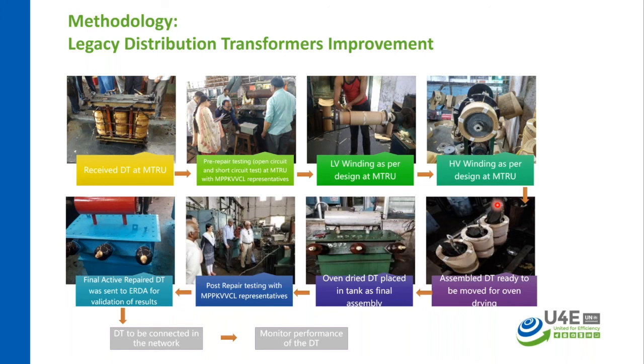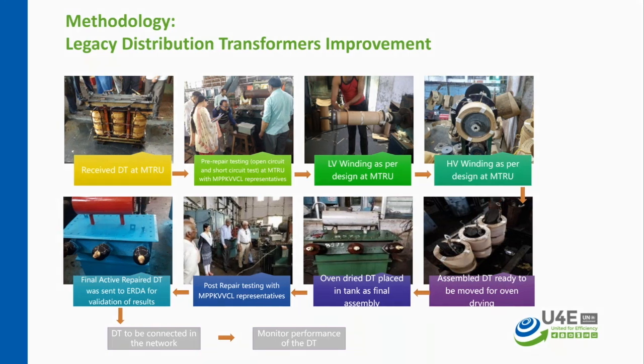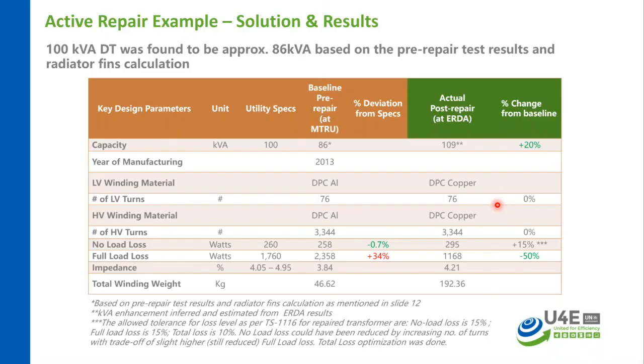And then after the transformer is repaired, the same transformer's new performance is measured as per the IEC standard, and then the improvement for this transformer will be rewarded to the repairer through a performance-based contract term. So the actual result, actual case, I just want to share for your benefit: the 100 kVA transformer, I think the rating is also very similar to Mozambique here.